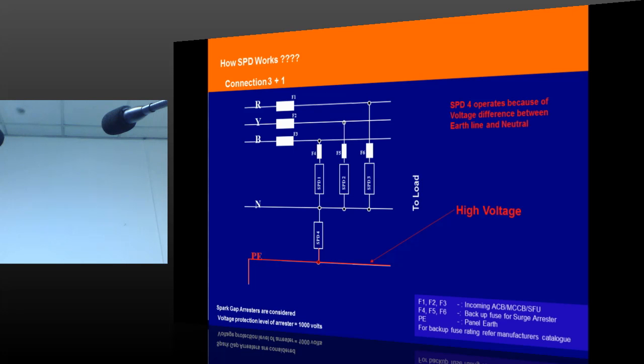Immediately, potential difference between PE and neutral ensures that this particular SPD is in operation. It is operated because once the potential crosses 1 kV, there is a flashover, and due to the flashover, both the lines are connected together. Now PE and neutral are connected together. It means there is no potential difference because these two are connected together through the SPD. Immediately, the same potential difference will be experienced between neutral and the other phases. SPD 1, 2, 3 operates, and all the other lines are also connected to the neutral. And basically, what we are achieving is equipotentialization, equal potential everywhere. And I told you, SPD is creating a kind of a short circuit situation. But now to select and install SPD, there are other conditions which need to be met. But basically, what SPD does is this.